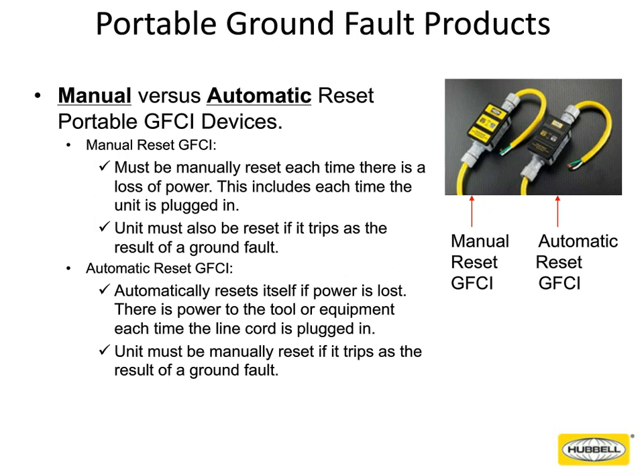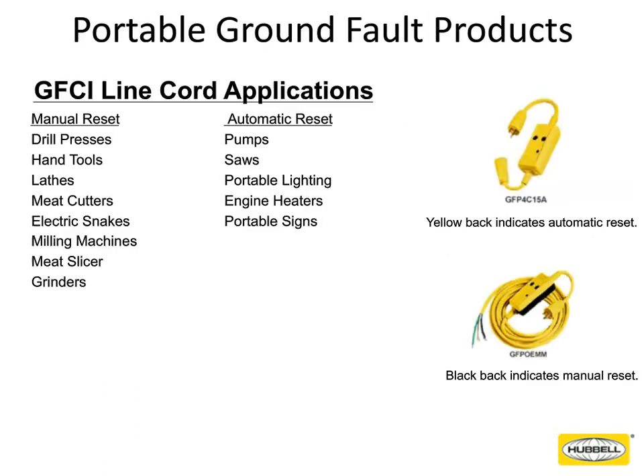There are a couple of applications where you might want to use the manual and the automatic versions. To give you some examples, when you're using power tools, and I mean 90% of the applications you're going to have, you're going to want a manual reset unit. If you're working with a lathe or a hand tool, you don't want somebody to plug it in and automatically have power there. You'd rather have the user be forced to manually reset the ground fault and know that there's power there.